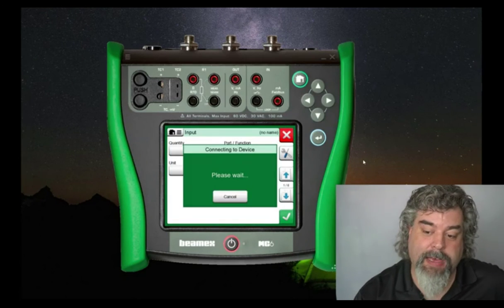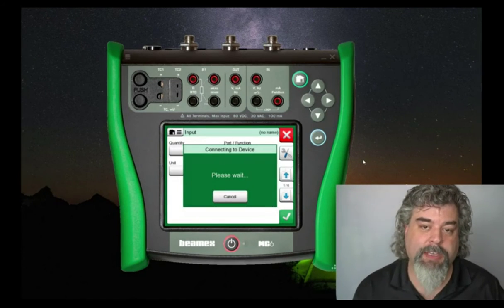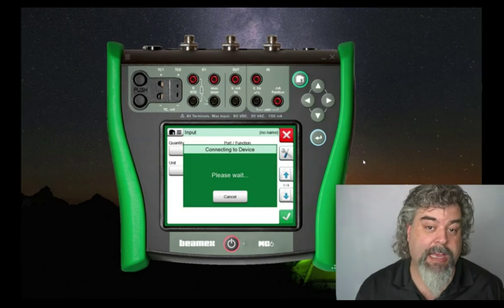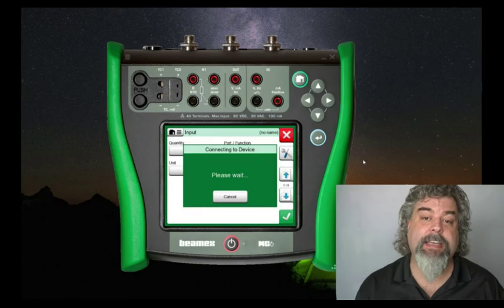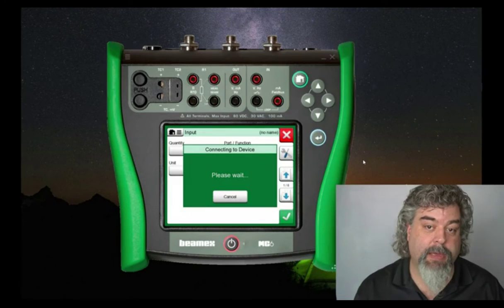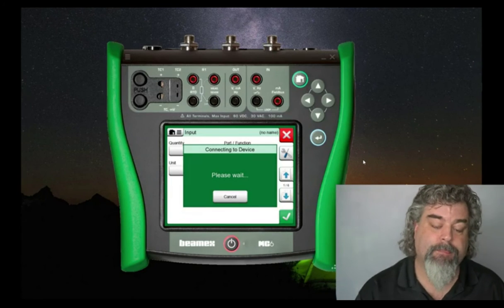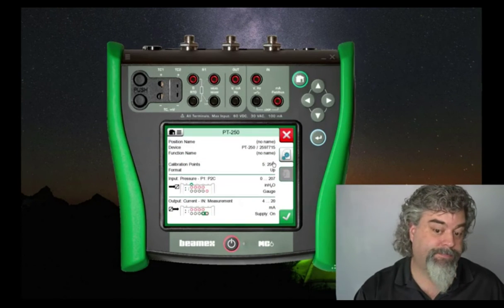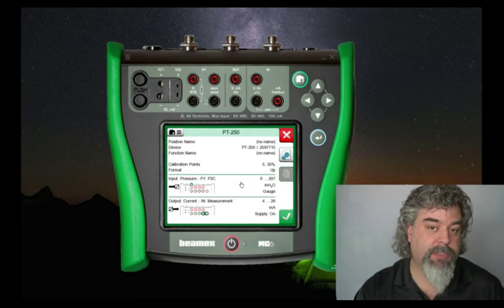And there's a secret button here on the top left. I'll do get mapped values. This will fire up the HART communicator and allow us to build a tag. It'll pull over the input range, the output range, the tag name, the serial number, the make, the model, all the core info needed to perform a calibration. And this is where we come to the key point of how do we do this calibration?